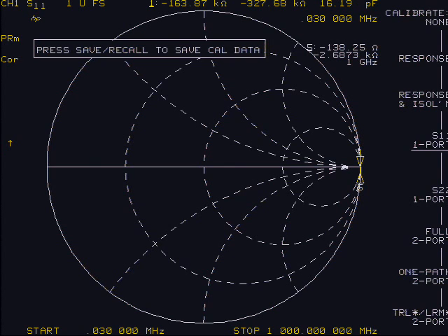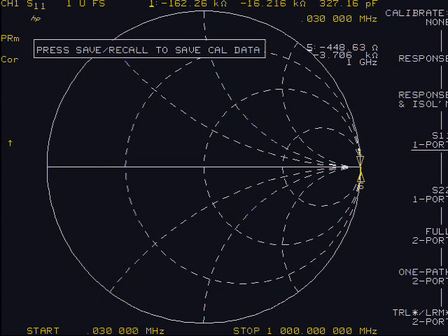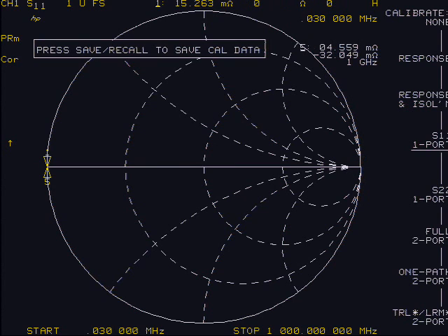If you check each of the other cal components, open or short, you should see a similar condition. If any of the three loads are not close to their correct position, redo the calibration.